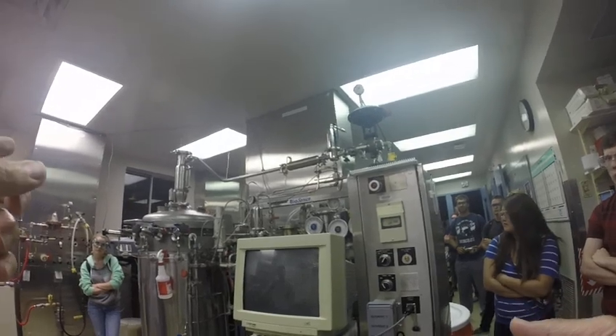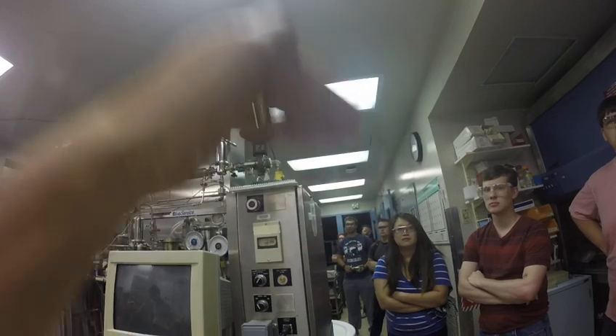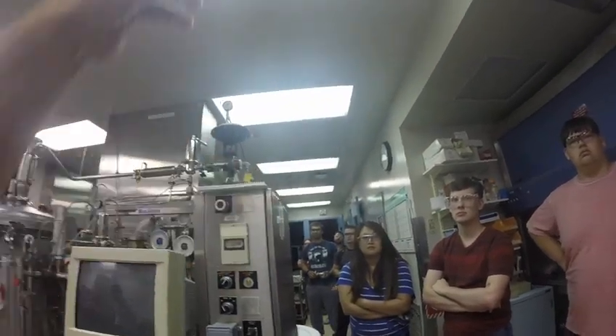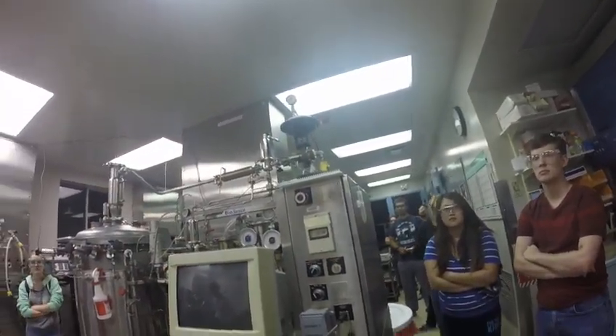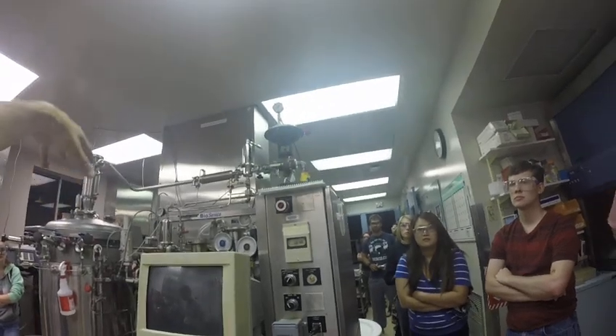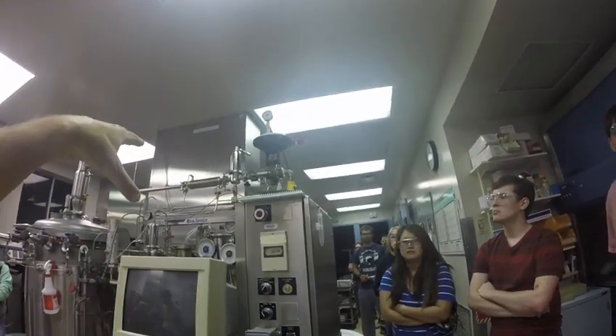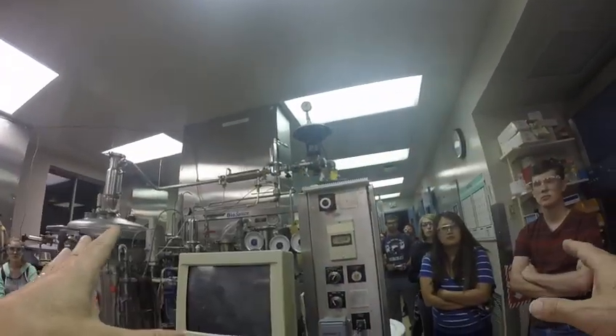It's by controlling pressure. Okay? Because it's at saturated steam, because of the nature of the way a steam trap works, but by controlling pressure is how we can control temperature in that sterilization cycle. During the actual operation of the reactor, it's entirely different.